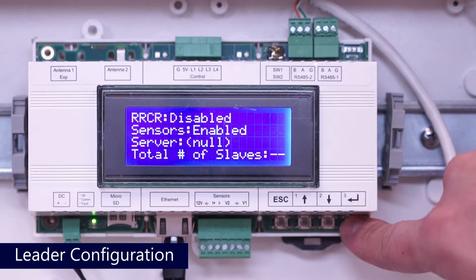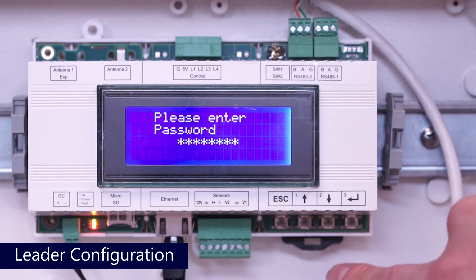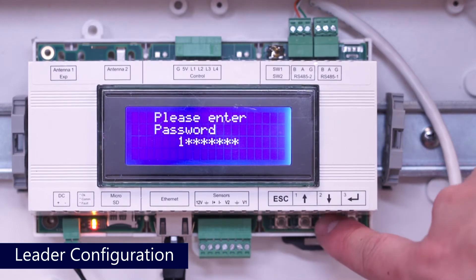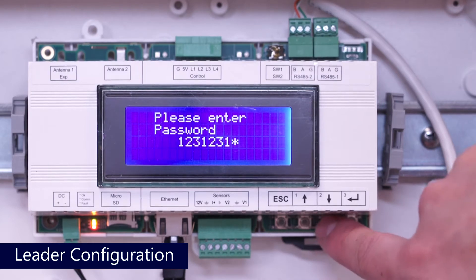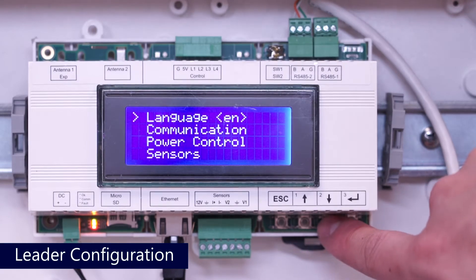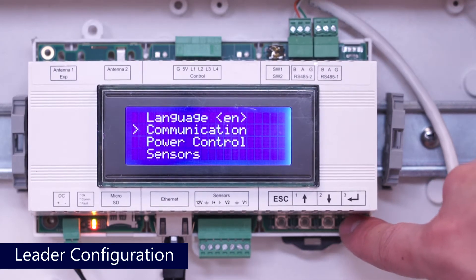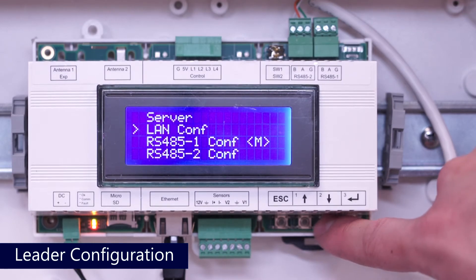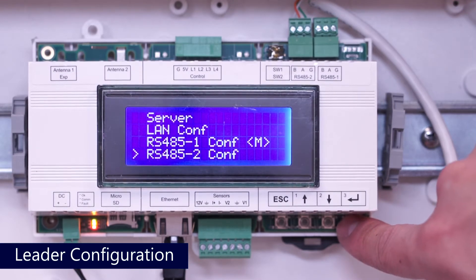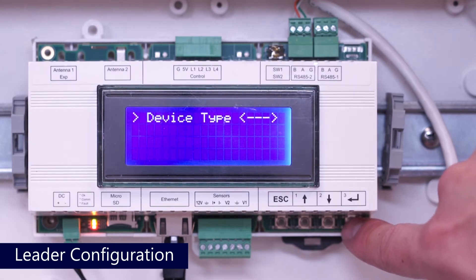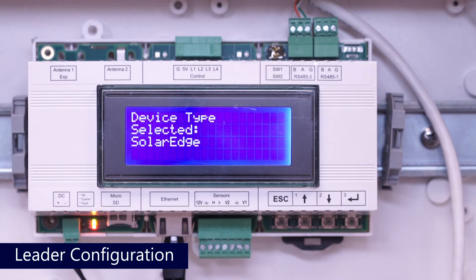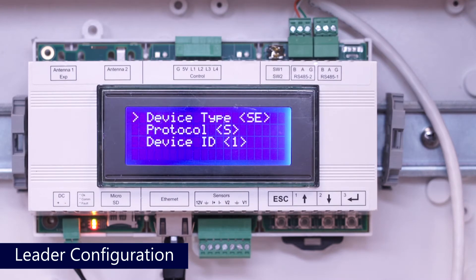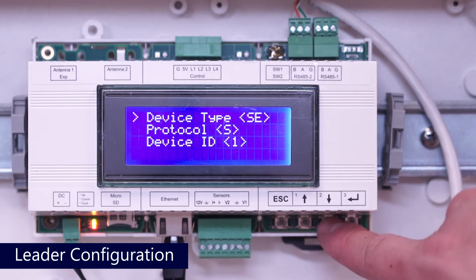To set up RS485 communications, long hold on enter and use the password 12312312. From the menu, scroll down to communications and press enter. Scroll down to your RS485 interface configuration and press enter. Select device type and press enter. Select SolarEdge and press enter. Next, scroll down and select protocol, then select master.